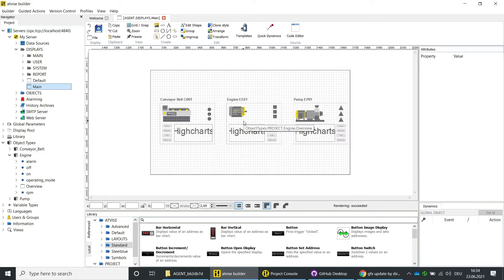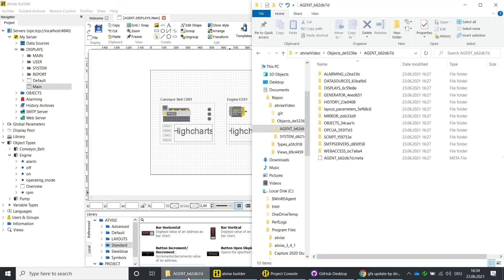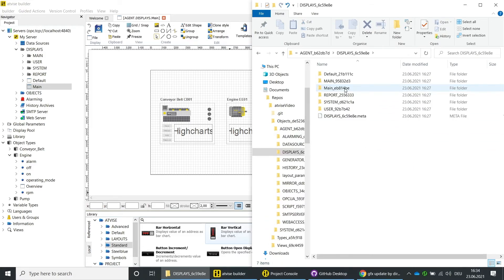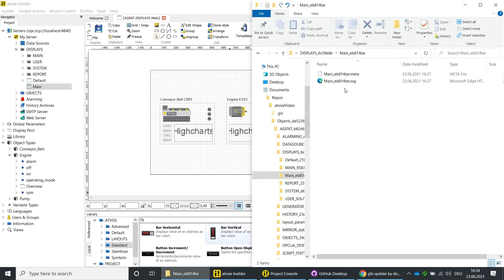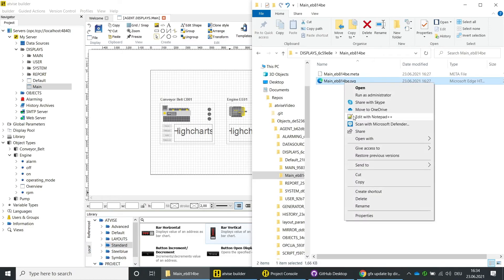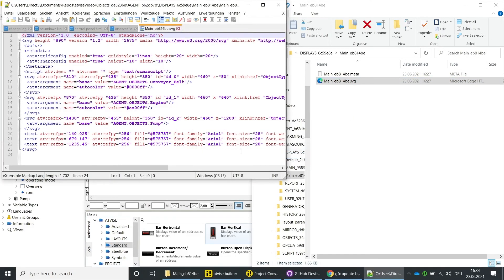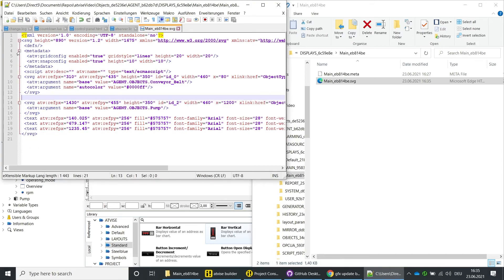Because you can access all files via the file system, you can also make changes in a text editor. For demonstration purposes, we will delete the engine object from the main display. Open Windows Explorer with the base directory, navigate to Objects, Agent, Displays, Main, and open the SVG file with a text editor such as Notepad++. Delete the SVG element of the engine object and save the SVG file.